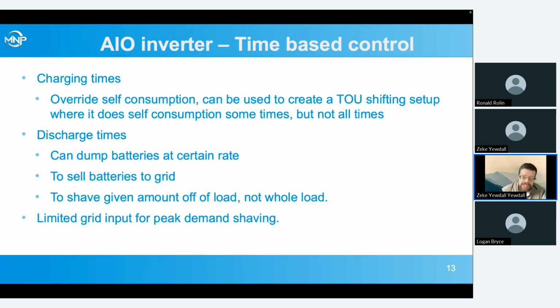Another situation that we run into is peak demand, where you may pay charges based on the peak kilowatts you draw from the grid, not just the energy use. Not real common on residential setups, but can exist. There, we actually have a completely different tool, where we set our grid input. We can set that, it comes default at 24,000 watts, that's 100 amps grid input. But we could set that much lower. We could say, I never want to draw more than 4,000 watts from the grid, and it will power more than that from the batteries.